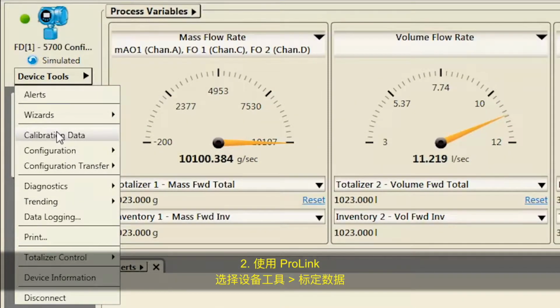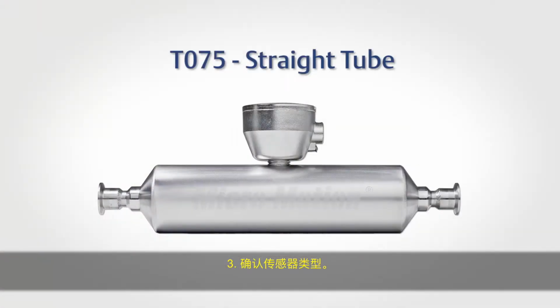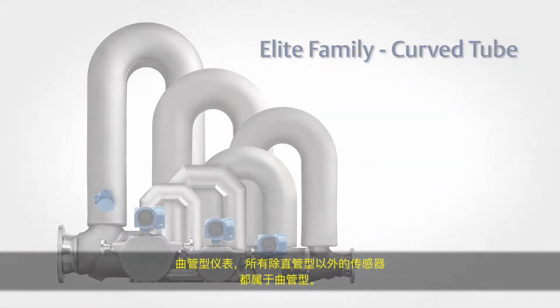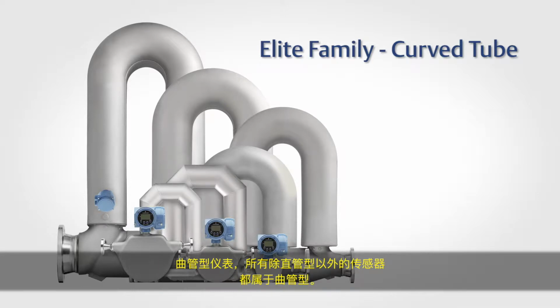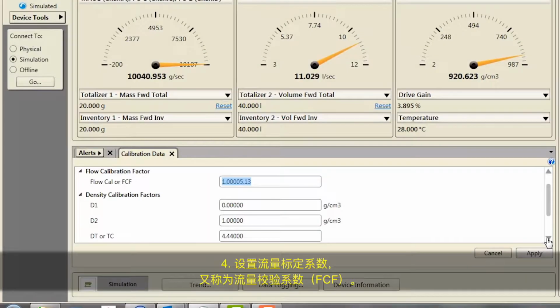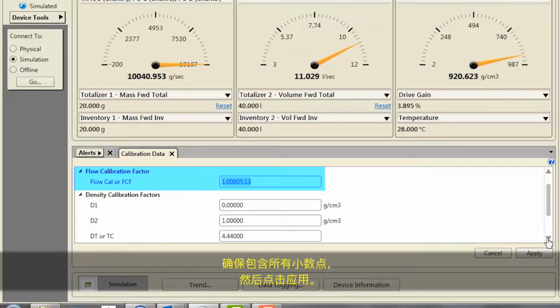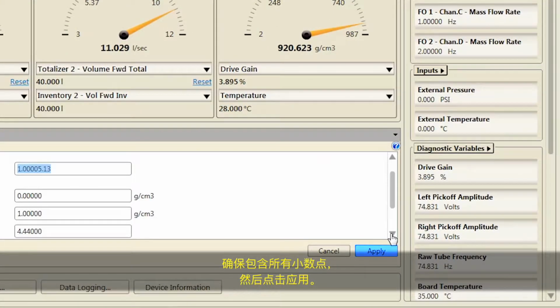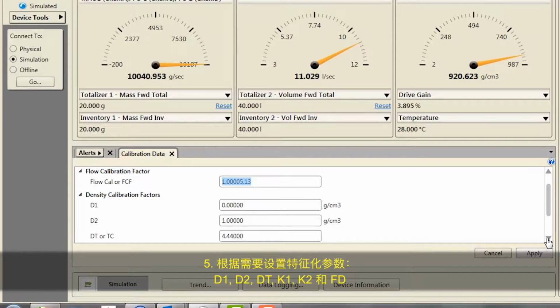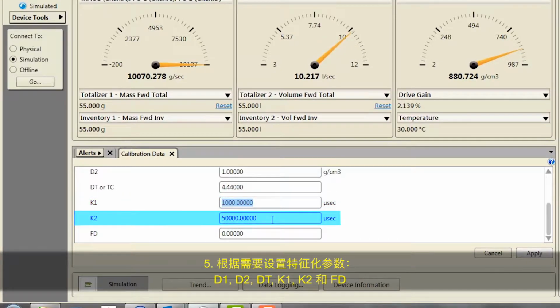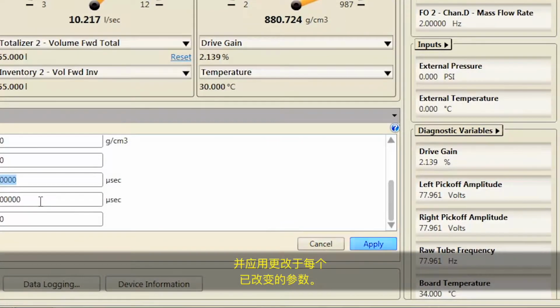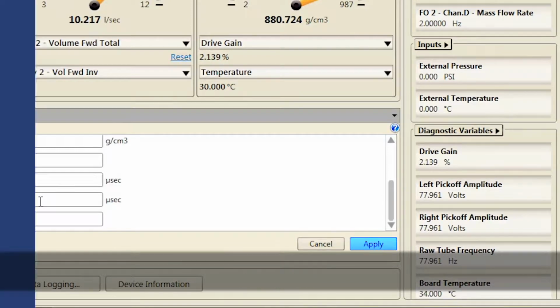Second, using ProLink, select Device Tools, Calibration Data. Third, confirm your sensor type, straight tube meter or curved tube, which would be all sensors except a straight tube meter. Fourth, set the flow calibration factor, also known as FCF or flow cal factor. Be sure to include all decimal points and then click Apply. Fifth, set the characterization parameters D1, D2, DT, K1, K2, and FD as necessary, and apply changes for each parameter that has been changed.